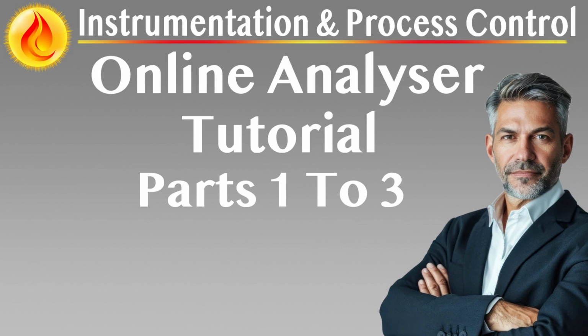Integration and interfacing. Online analyzers must be seamlessly integrated into the plant's process control and automation architecture. They typically interface via 4-20 milliamp analog signals, Modbus RTU/TCP, Profibus, HART, or OPC UA, depending on the type of analyzer and host system. Integration points must include not just measurement outputs, but also status flags, alarm bits, maintenance indicators, and diagnostic information.